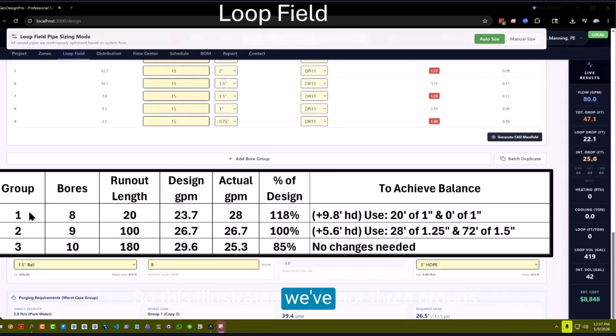So this illustrates we've got 3 groups. The first one's got 8 bores, second one 9 bores, the third one 10 bores. Significantly different as far as distance away from the building. Very unusual. Typically, groups might only be 20 feet apart. But here, the site dictated we spread them way apart. Our design flow rate is basically we want the same GPM per foot of pipe on all our vertical bores. And that's how we calculate the design GPM.